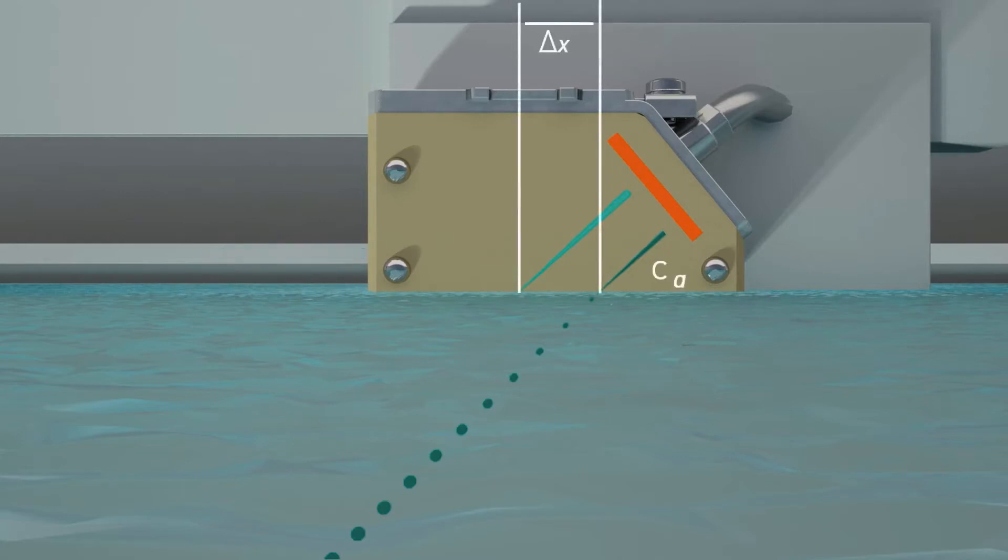This shift causes a decrease in the ultrasonic signal's path length by delta l, and accordingly a decrease in total transit time by delta t. As the transducer constant is the ratio of the local shift to the change in transit time, the aperture calibration allows for the most direct and thus the most precise calibration possible.